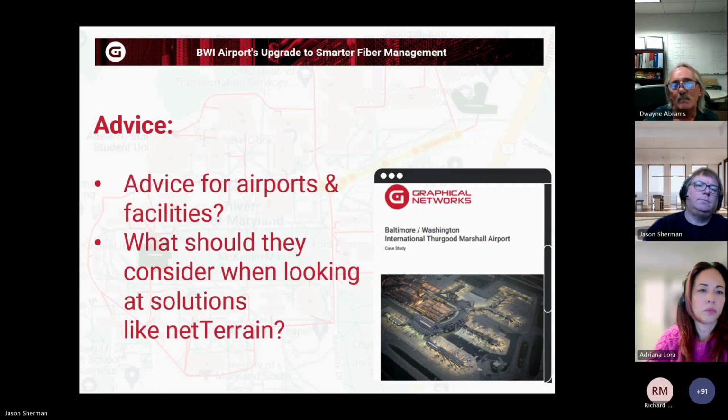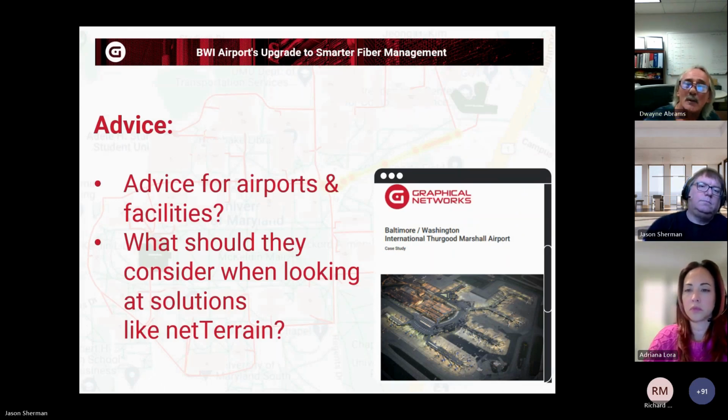Having a unique numbering scheme is absolutely key. Here we have door numbers. Every door you enter or exit has a number on it, so I use that as an identifier for that comm room. Then I go with a row number for all the racks, a rack number, a panel number, and then a port. That's our standard here. Nobody deviates from that. And once you have all that, you're good to go. You just take it away.